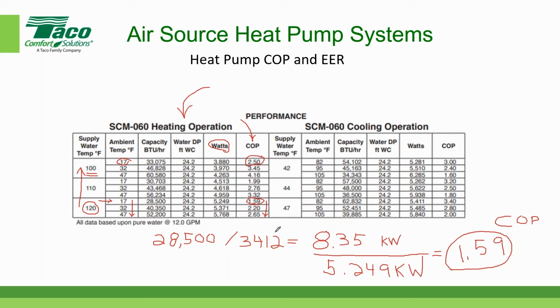The majority of the heating hours, let's just take the Northeast, for example, the ambient temperature average on a daily average is around 30 degrees Fahrenheit, which means that if you have a very low temperature distribution system and you can live with 100 degrees discharge water temperature, you can have a significantly efficient unit, because if your average temperature is 32 degrees, you're going to get 3.45 units of heat for every unit of electricity. And you can see what happens in the mild weather.